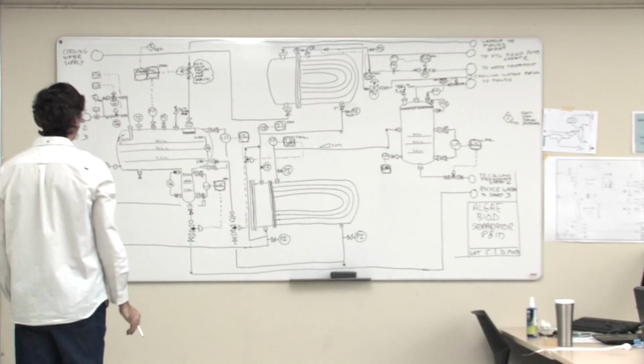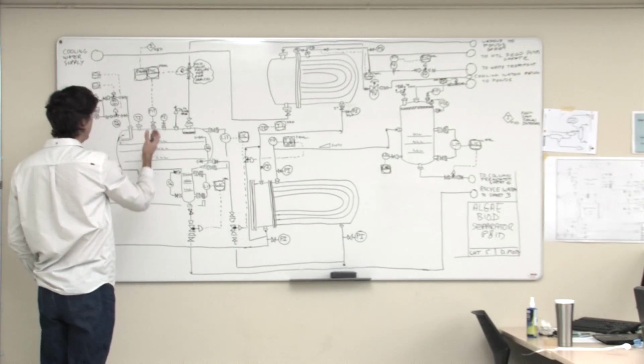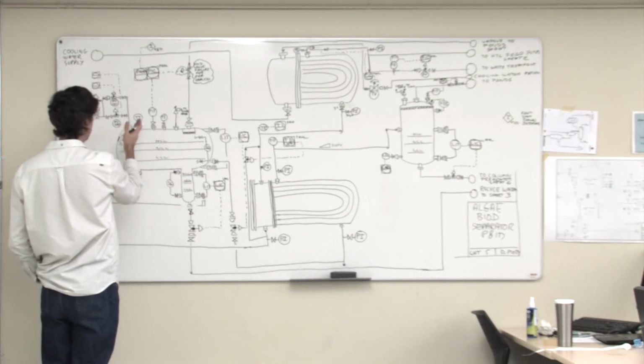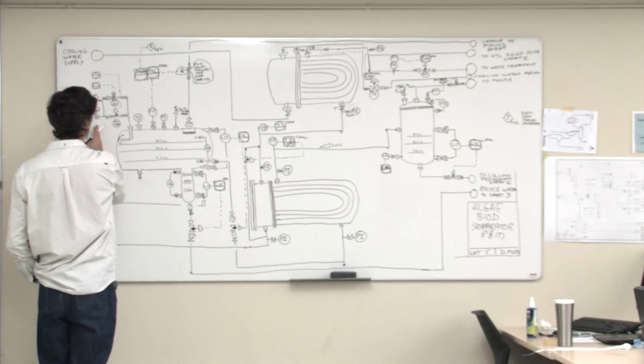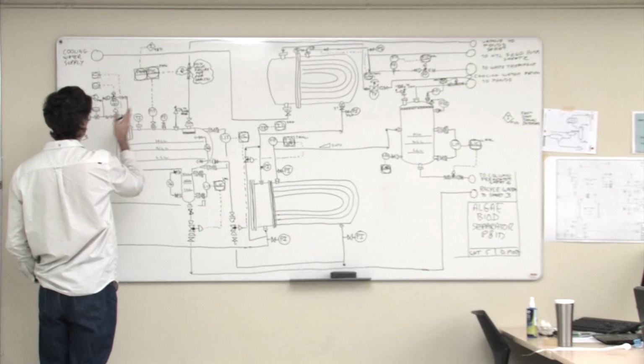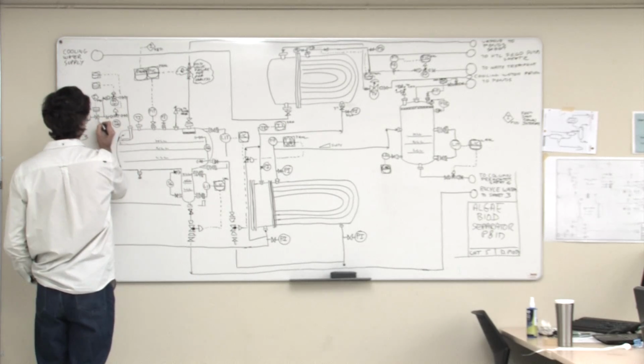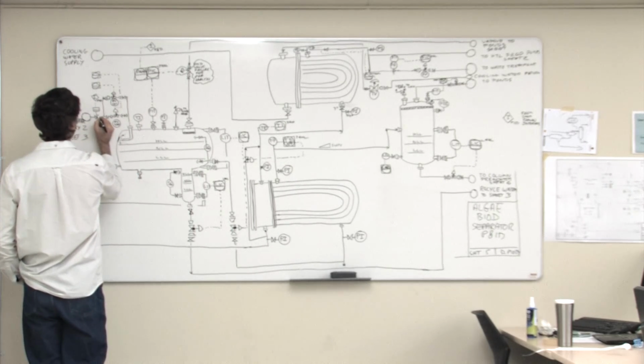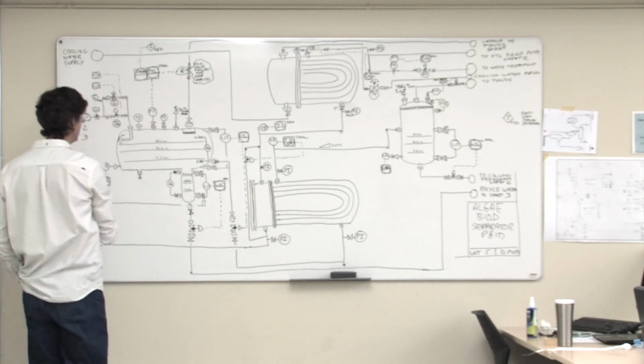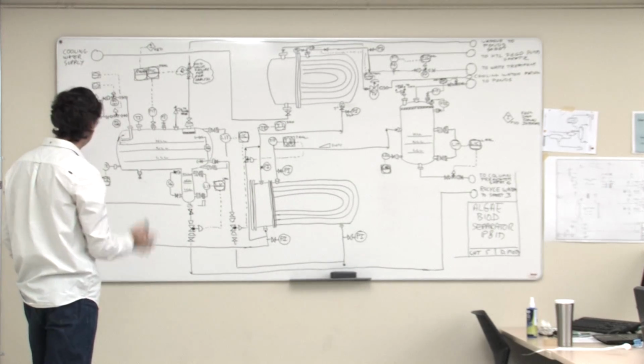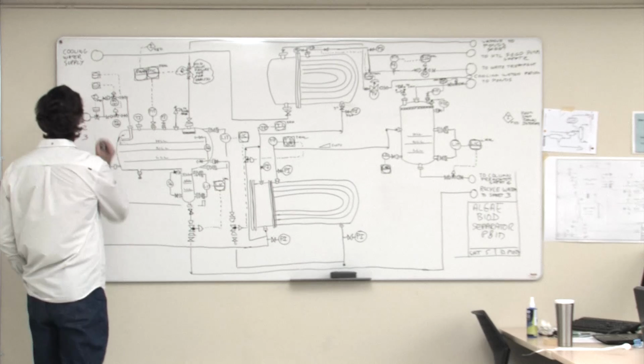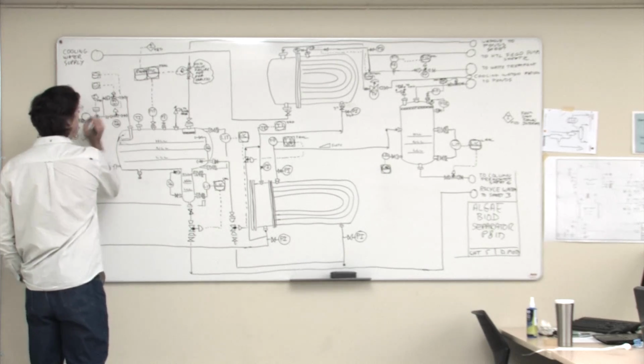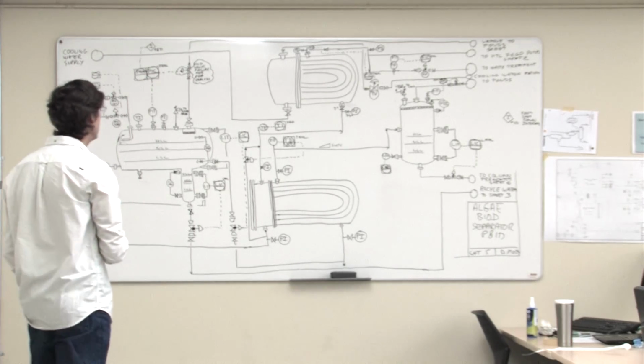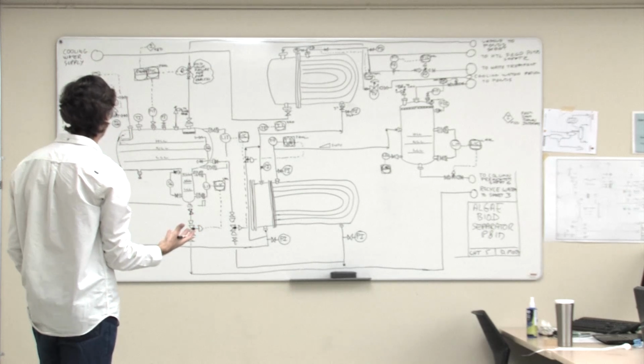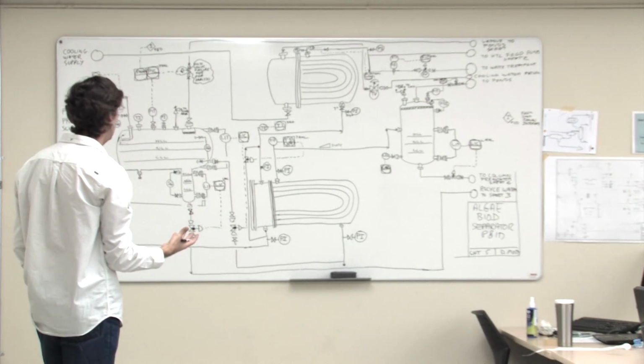So that would, if we do get high pressure, then as long as it's not a fire under the unit, that pressure almost certainly must be coming from the upstream side. We're going to shut this feed pumps off, and we're going to isolate it with this valve that normally stays open all the time, and it just is a gate valve that would close. And we haven't shown any cascade loops. Actually, that's bad. We should at least put a cascade loop on so you guys know what a cascade loop would look like. I can't even think of where a good application of a cascade loop would be here.